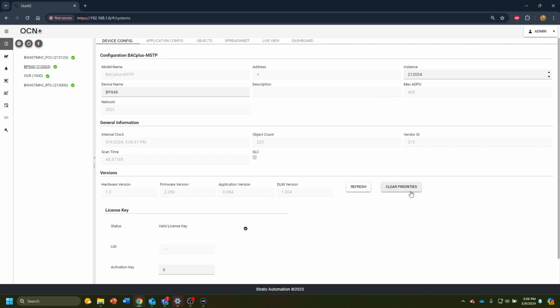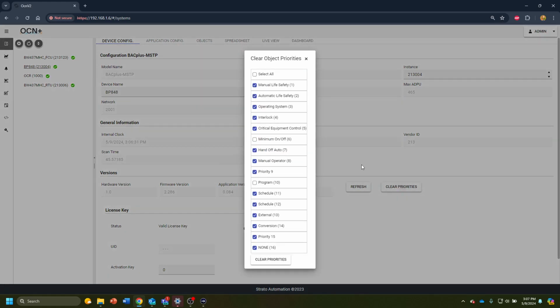Additionally, let's say I have a bunch of overrides—manual overrides for commissioning purposes, or I just have conflicting priorities and rights going on in the background. I just want to set everything straight and work from scratch. If I click this clear priorities button, I can write null to any priority for every object on my device. So if I hit select all, it's going to highlight all of them.